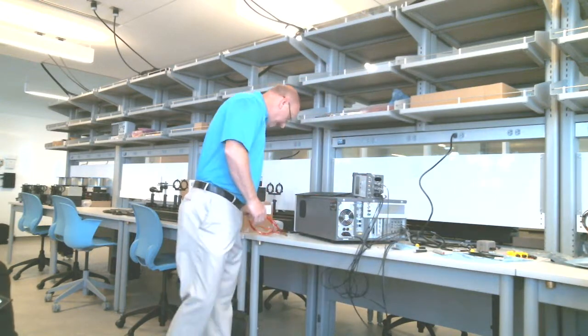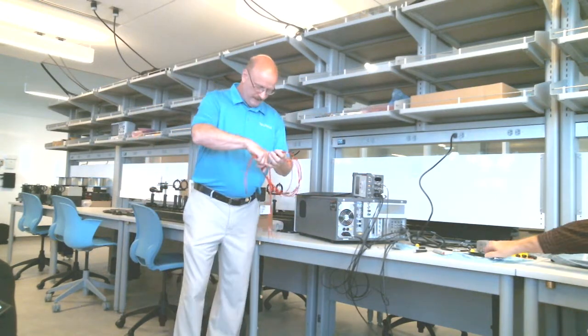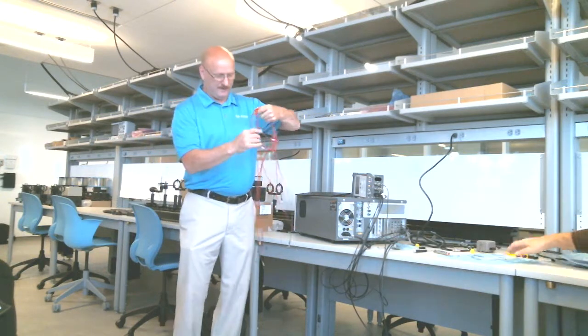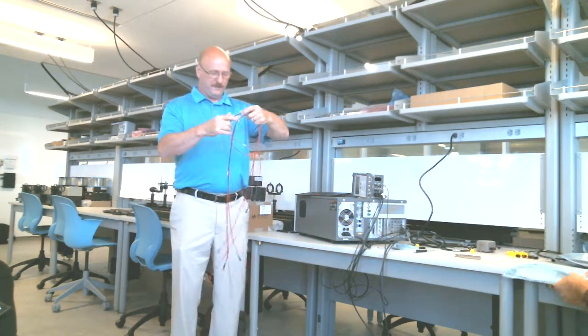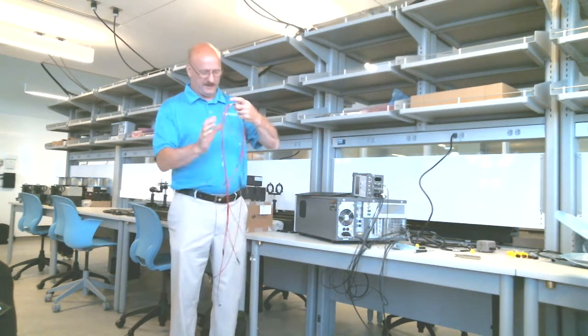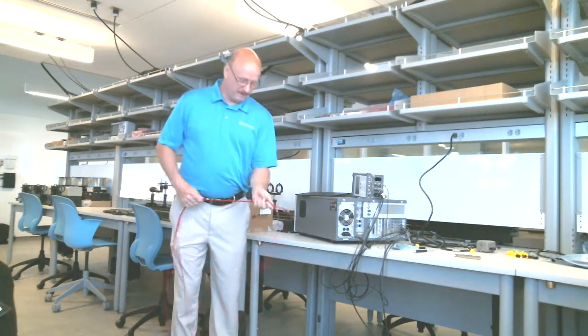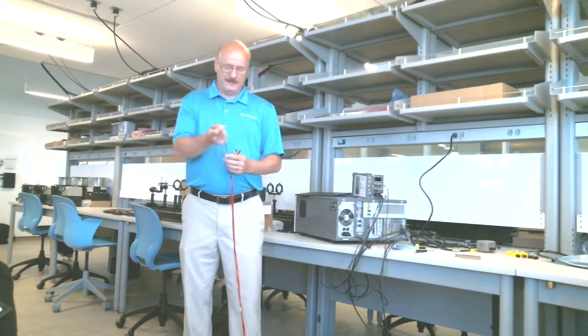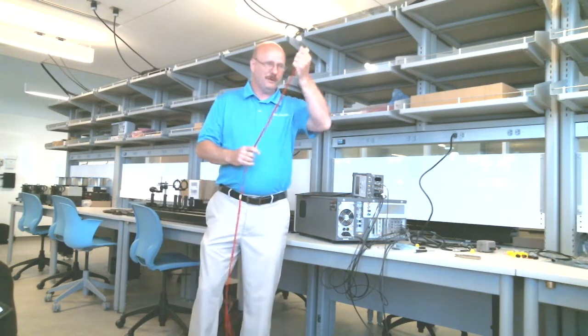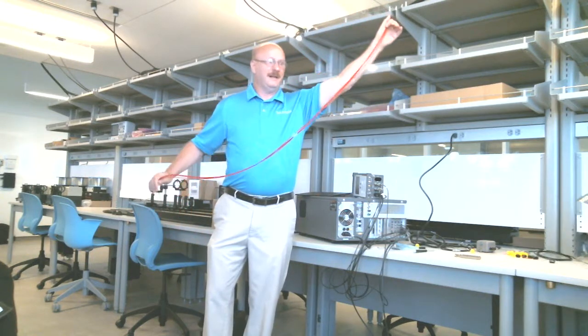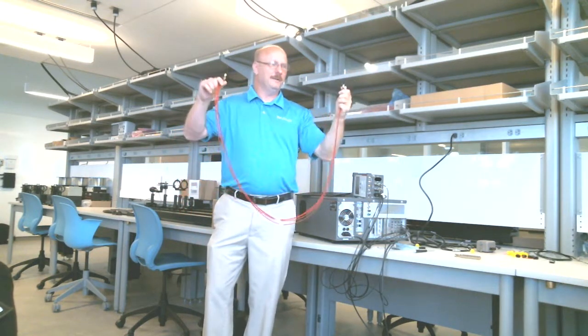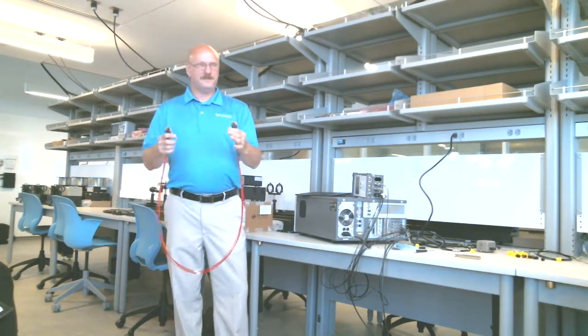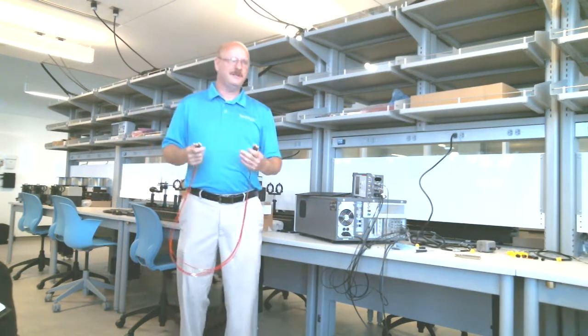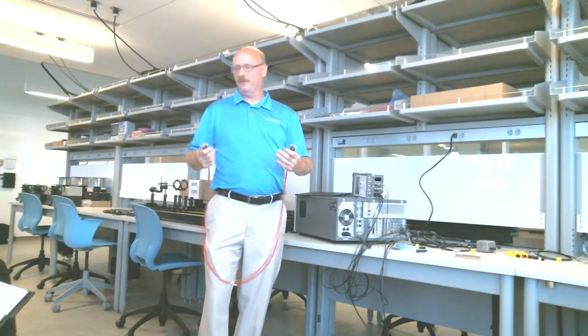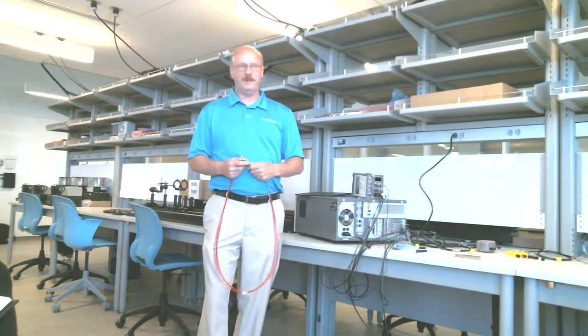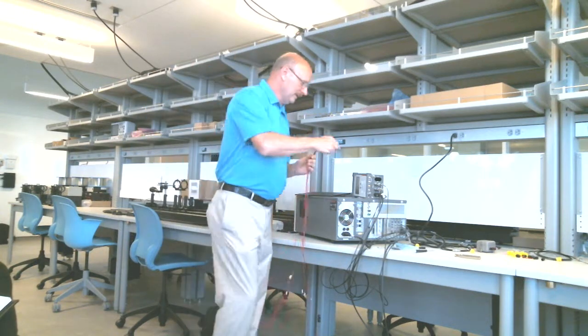Now, CV. Here are the CV cables. Very important that you use these cables with our CV meter. Our CV meter is optimized for these cables. One of the things being the length. It's an AC measurement, so there's a phase component. So all these cables have to be identical in length and makeup, right? Because if your phase error gets off by more than 90 degrees due to different length cables, it will throw off the bridge on the LCR meter, and you'll get all kinds of crazy results.